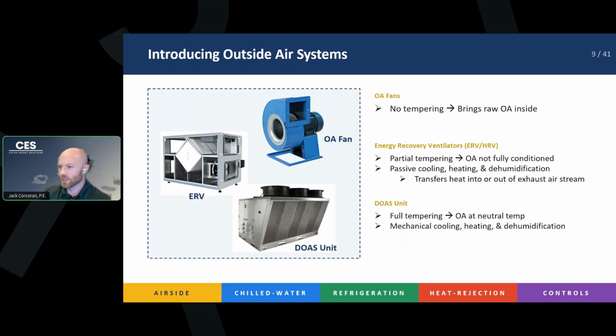And lastly, you can use a full-on DOAS unit. DOAS stands for Dedicated Outside Air System. This is where you're going to have your mechanical cooling and heating. You're going to have some sort of heat pump, your DX coil, or a chilled water coil. You need to add in work in this phase. This is your mechanical cooling with compressors. This is going to allow you to get your outside air to whatever temperature and humidity you need. If you have a very strict requirement on your temperature and humidity, you're going to need to put in work. You have to add energy in order to get rid of the added latent and sensible heat that we're bringing into the space. So our three systems: outside air fan, ERV, and a DOAS unit.